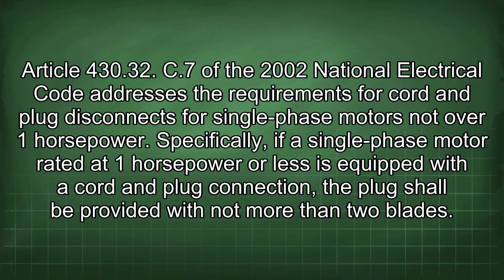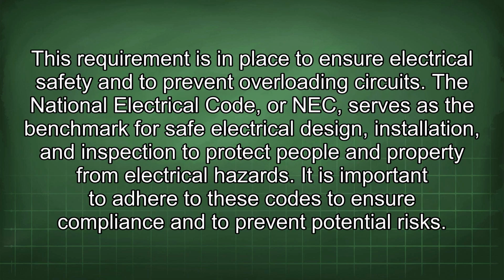430.32 C7 of the 2002 National Electrical Code addresses the requirements for cord and plug disconnects for single-phase motors not over 1 horsepower. Specifically, if a single-phase motor rated at 1 horsepower or less is equipped with a cord and plug connection, the plug shall be provided with not more than 2 blades. This requirement is in place to ensure electrical safety and to prevent overloading circuits.